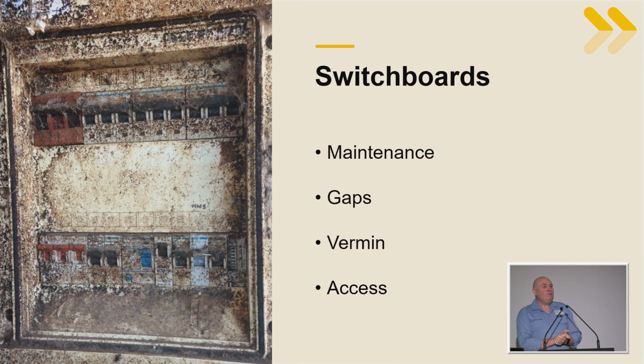Switchboards actually require a bit of maintenance, and keeping them clean can not only ensure they function correctly, but also keeps them safe. It's pretty clear from this photograph that the safety switches have never been tested in this switchboard. They've got an internal mechanism - it's mechanical, like anything mechanical. If you don't open a gate when you want to open it, it's not going to open properly, it's going to be stiff, it's going to bind up.